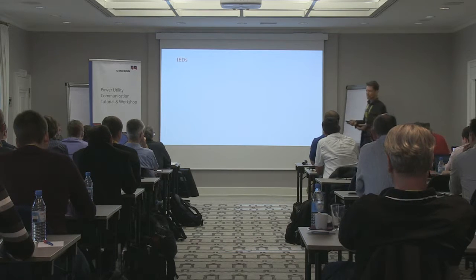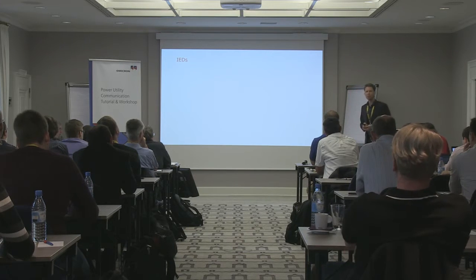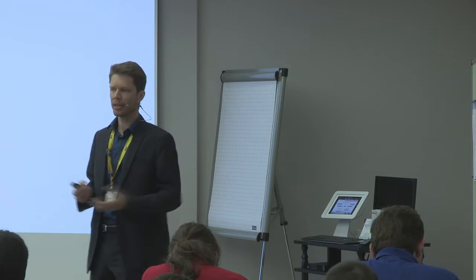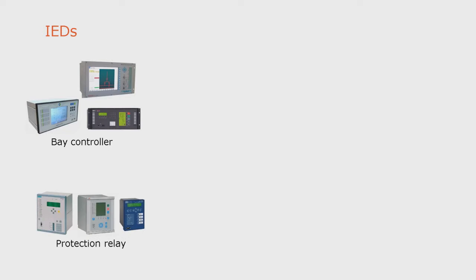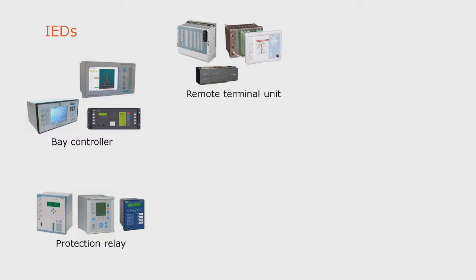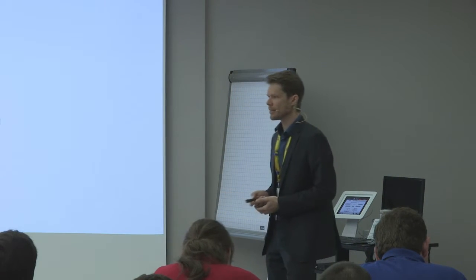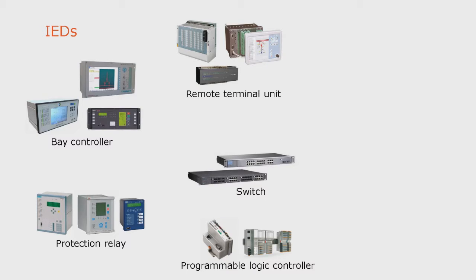When we talk about IEDs, I would like to sum up which IEDs we typically face. So we have the bay controllers — they are controlling the circuit breakers, measuring, and maybe they have some protection functionality integrated. Speaking about protection, we have the protection relays as IEDs. We have also the remote terminal units or gateways as IEDs. And we also consider the switches as IEDs; they are now also able to speak 61850, not only SNMP. Even PLCs are IEDs and some of them already speak 61850.